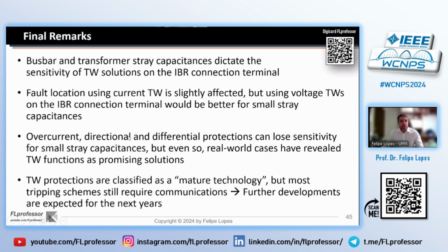We could see also that overcurrent, directional, and differential protections can lose sensitivity for small capacitances, but the real-world cases that we have analyzed so far have shown that these functions are indeed promising solutions. And it shows that the stray capacitances in practical situations tend to be sufficient to guarantee the sensitivity of these technologies. But I have to say that a previous study on the stray capacitances is recommended to have an idea about the sensitivity of these traveling wave protections. And finally, the traveling wave protections are classified as a mature technology. This is why I do believe that further developments will be presented in the next years.